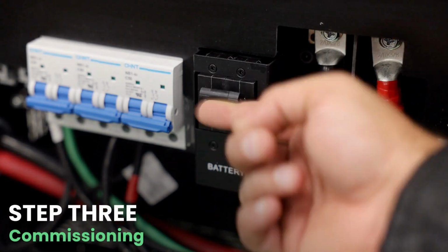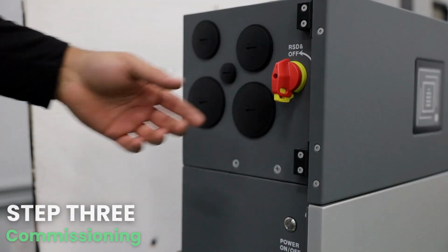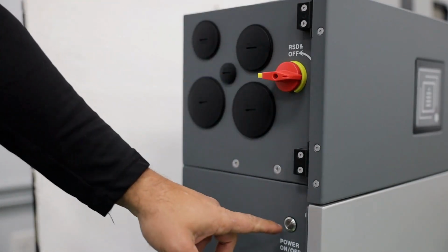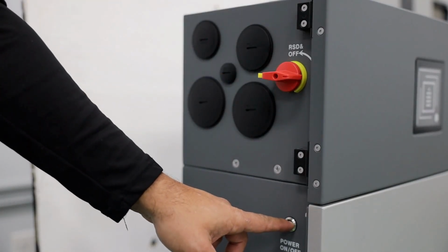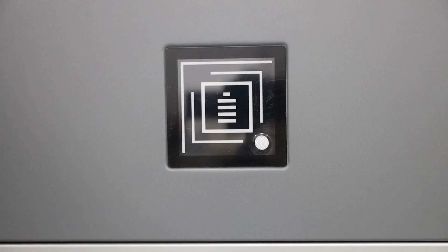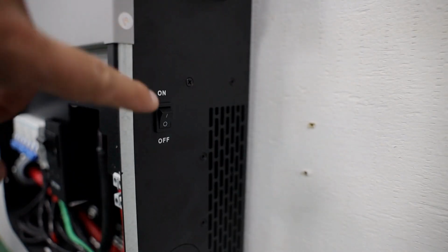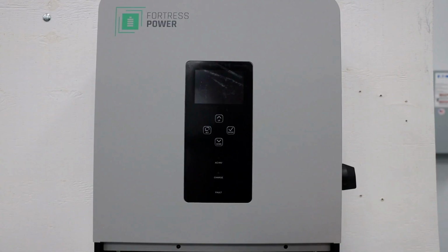To commission the system, first turn on the battery breaker at the inverter. Next, energize the battery. Then place the inverter switch, located on the right side of the inverter, into the on position. Confirm that the inverter booted up. Note, the inverter comes pre-programmed to work for off-grid and self-consumption applications.